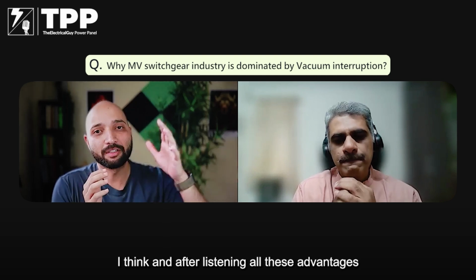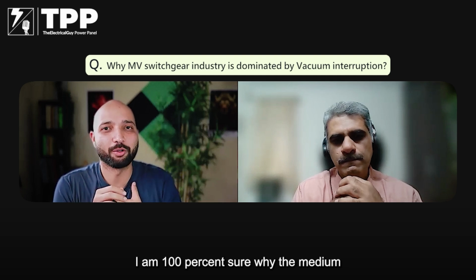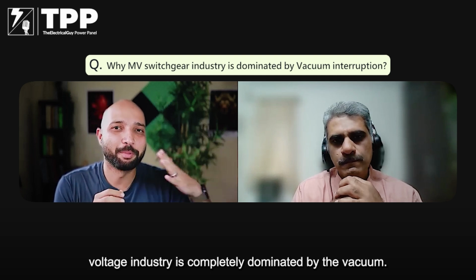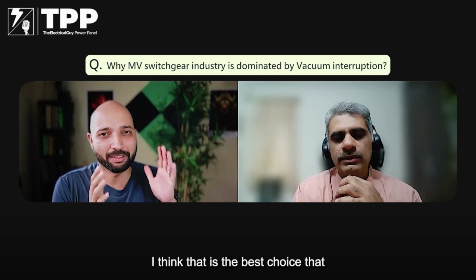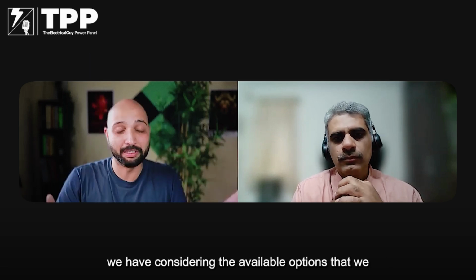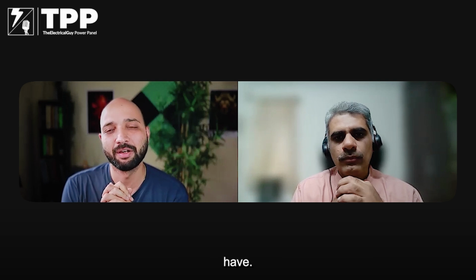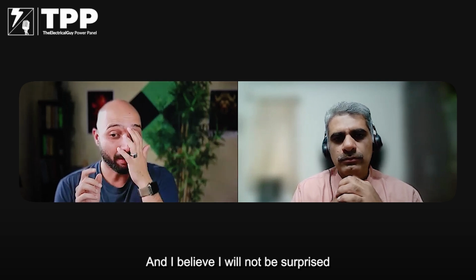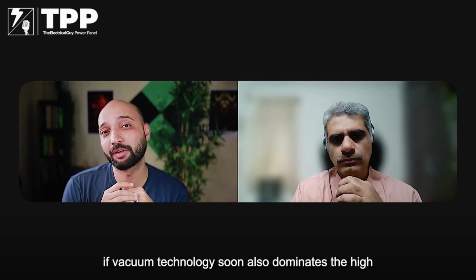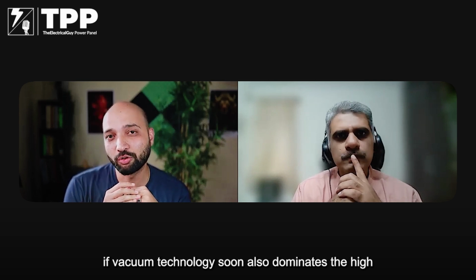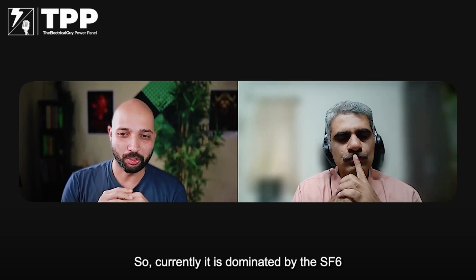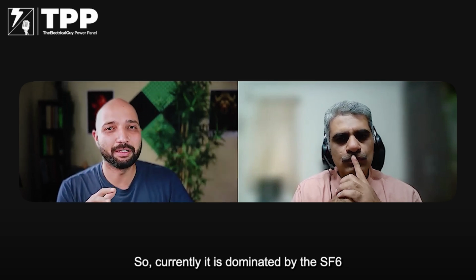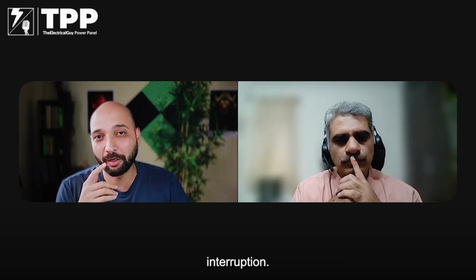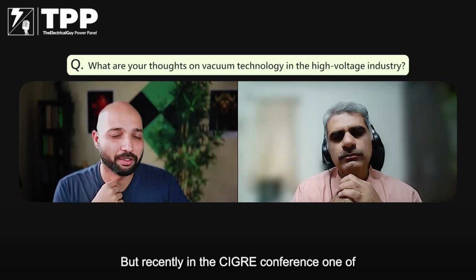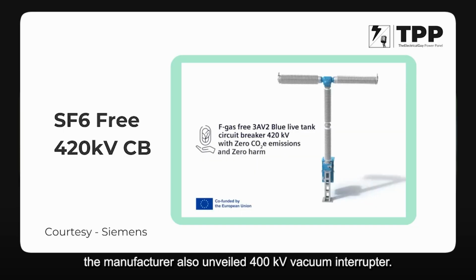Correct. I think, after listening to all these advantages, I'm 100% sure why the medium voltage industry is completely dominated by vacuum. I think that's the best choice that we have, considering the available options. Yes, vacuum is the best choice, and I will not be surprised if vacuum technology soon also dominates the high voltage market. Currently, it is dominated by SF6 interruption. But recently at the CIGRE conference, one of the manufacturers also unveiled a 400 kV vacuum interrupter.